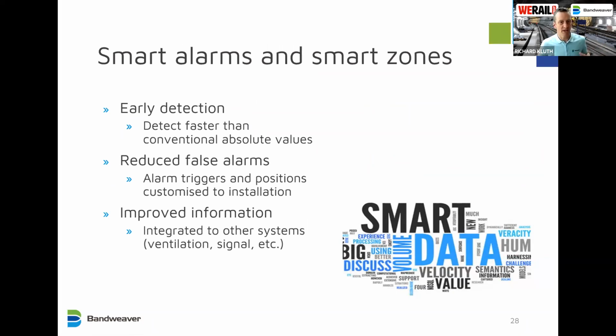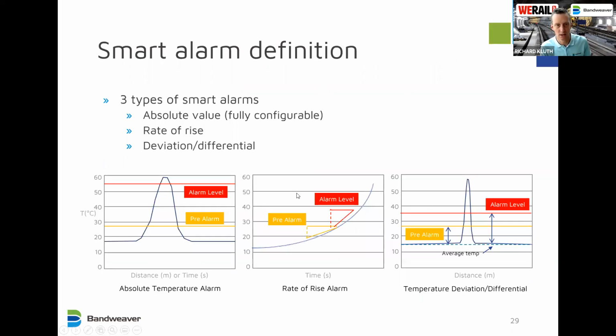So moving into smart alarms and smarter zones, which I said is really the heart of this technology. The key benefits are early detection, detects faster than conventional alarms, and reduced false alarms. You can customize each specific environment zone to the environmental conditions to really hone in on it, to reduce any potential alarms from that. And you get improved information, the temperature data, precise location, the accurate temperature means you can use this for ventilation signal control, which we'll look at.